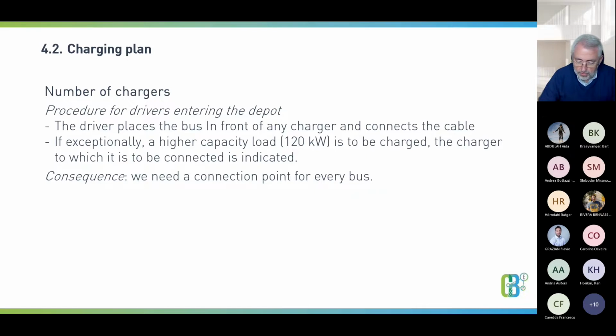Currently, only one bus can be connected to the second connection point, which is not charged directly, because the second connection on this charger is not active as long as 120 kilowatt charging capacity is drawn from the first point. If such situations occur regularly in an operation—here it's only marginal—it's advisable to install a portal with the bus number and indication of the charger where they should place the bus, visible to the driver entering the station or depot. The consequences of this way of working, and of the planning I showed before, is that we need a connection point for every bus.